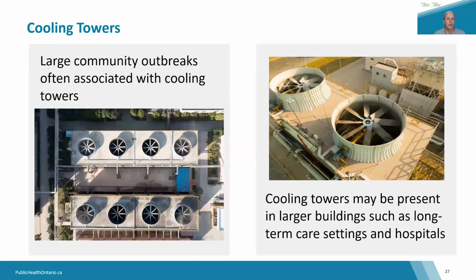So as seen in the polling question, and likely you've seen in the news over the past summer, cooling towers are also considered a main source of Legionella. These images here just show examples of rooftop cooling towers that you may see on larger buildings. So cooling towers can be part of a centralized cooling system for large buildings, including long-term care homes and hospitals. And most cooling towers operate seasonally during the warmer summer months when it's hot outside and cooling demands inside are high. So very simply, these structures contain water and fans to remove heat from the air.